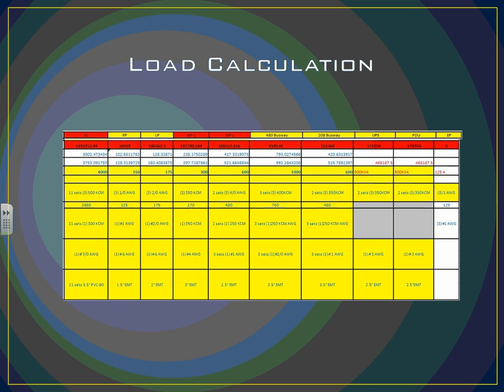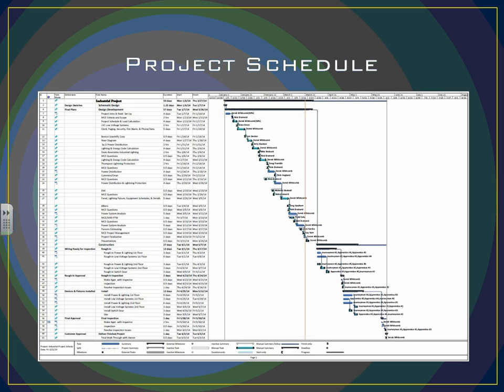And then from that point on, we're able to use that information to size our wiring. So we can go from that sizing of three-phase wiring, which allowed us to do that also for our neutrals and our grounds. And then from there, move into the project schedule.